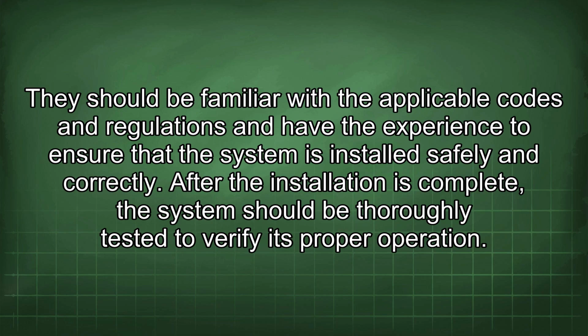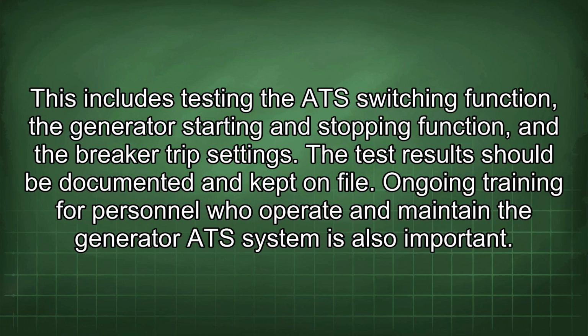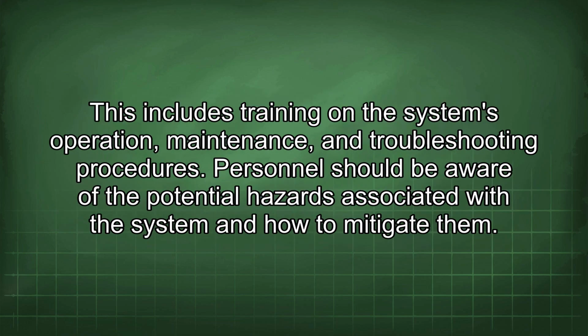installed safely and correctly. After the installation is complete, the system should be thoroughly tested to verify its proper operation. This includes testing the ATS switching function, the generator starting and stopping function, and the breaker trip settings. The test results should be documented and kept on file. Ongoing training for personnel who operate and maintain the generator ATS system is also important. This includes training on the system's operation, maintenance, and troubleshooting procedures. Personnel should be aware of the potential hazards associated with the system and how to mitigate them.